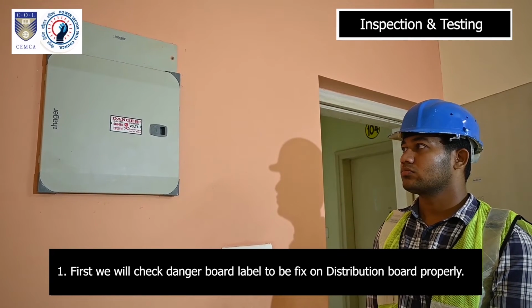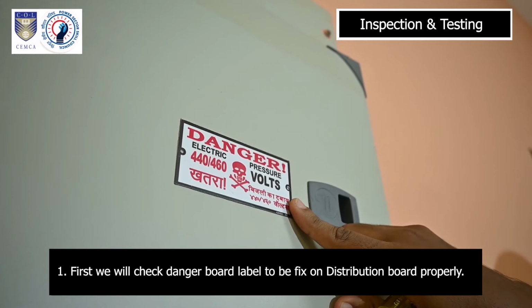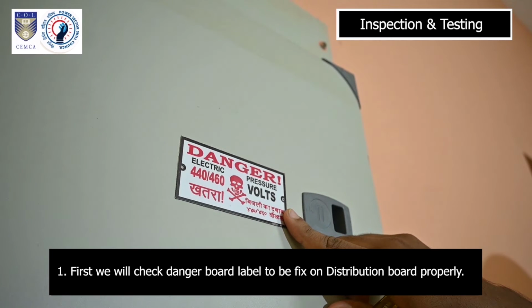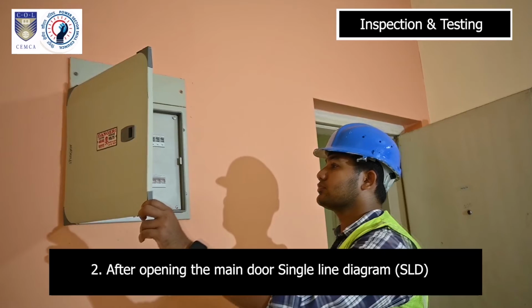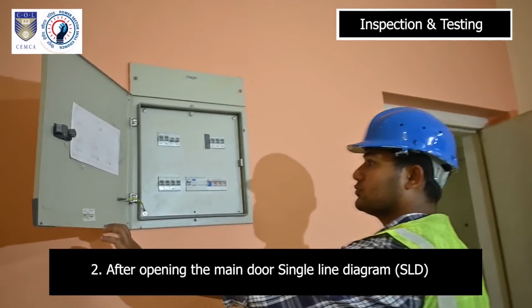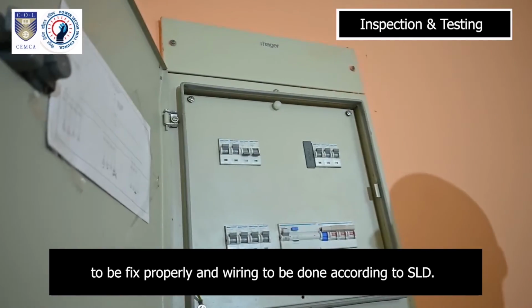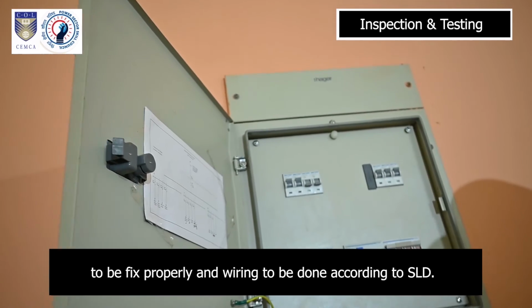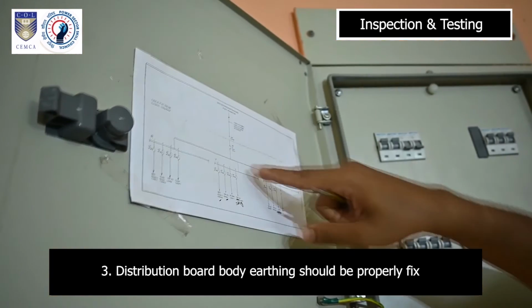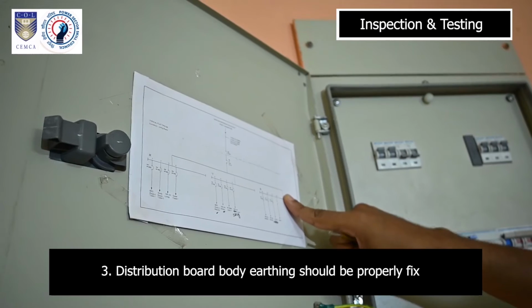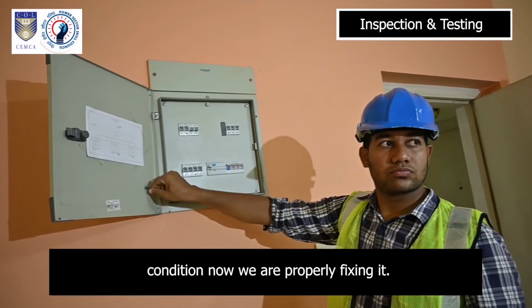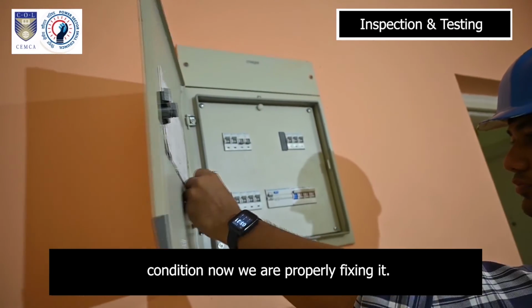1. First, we will check that the danger board label is fixed on the distribution board properly. 2. After opening the main door, the single line diagram (SLD) should be fixed properly and wiring should be done according to the SLD. 3. The distribution board body earthing should be properly fixed. As we are seeing here, it was found in a loose condition; now we are properly fixing it.